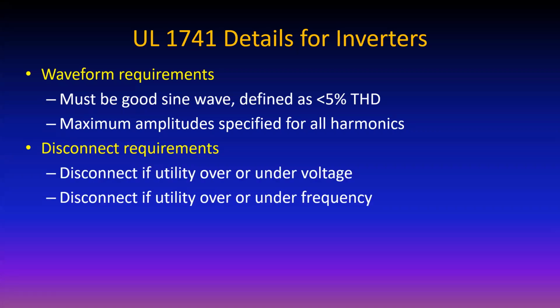You have to have disconnects, and the inverter itself has to do this automatically if it's over or under voltage, or over or under frequency, and the limits are specified. It's something like 10% over and 10% under on the voltage, and about 1% under or over on frequency. If you're at 60 hertz and you drop down to 59.4, I think you have to disconnect. It's somewhere like that. It's easy enough to find out what those requirements are. For the most part, you don't worry about it, because as long as the device is listed as UL 1741, it's already been tested and proven.